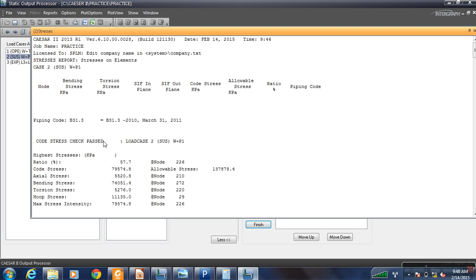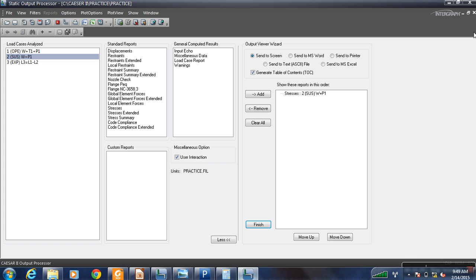The optimum or desired value is 50 to 80 percent. Around 50 percent is the desired value, and even if it is less than 50 it is possible, but if it is above 100 then you need to make changes. Here you can see only the load cases — we are assuming the weight of the pipe, temperature of fluid, pressure of fluid, and under seismic load as well.